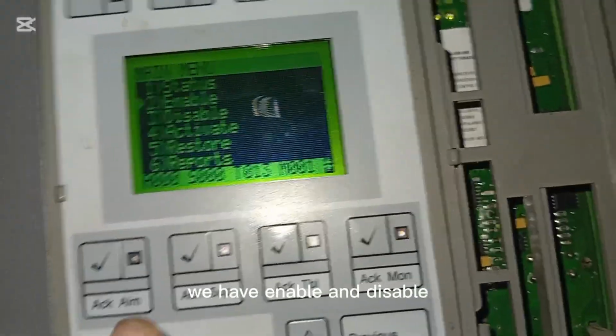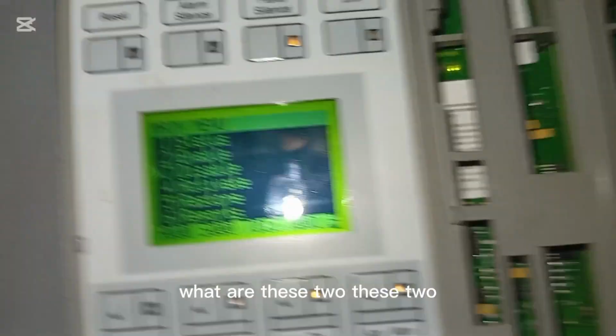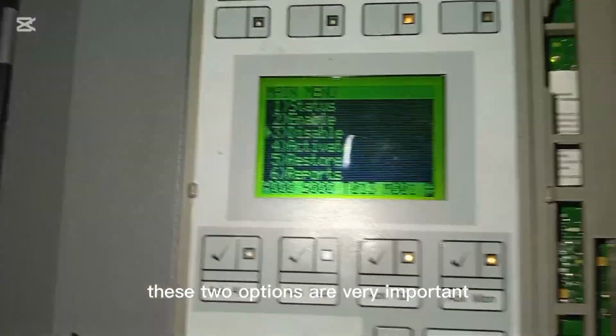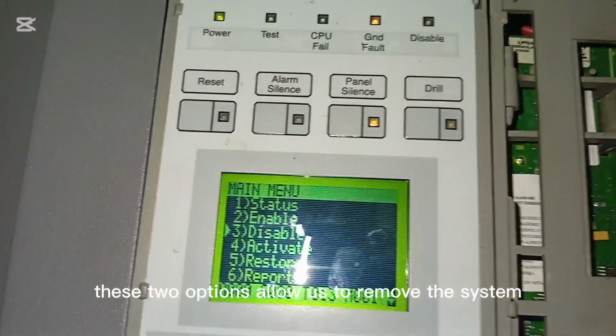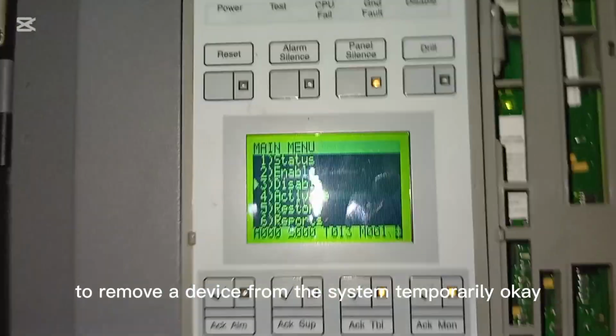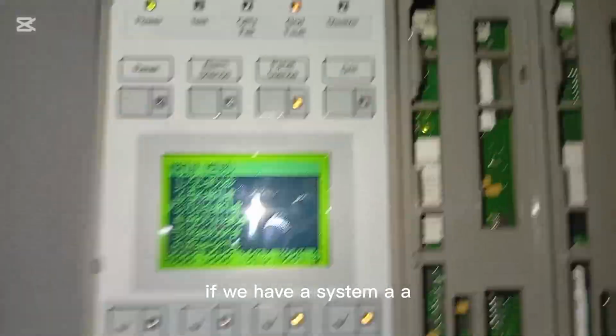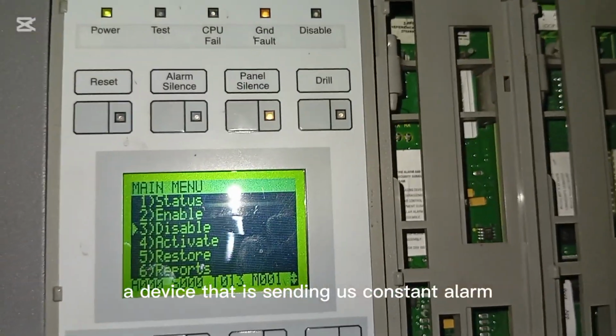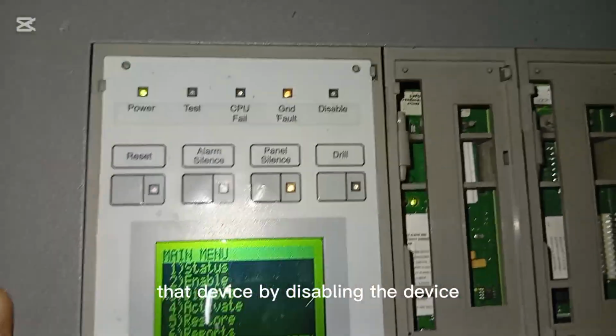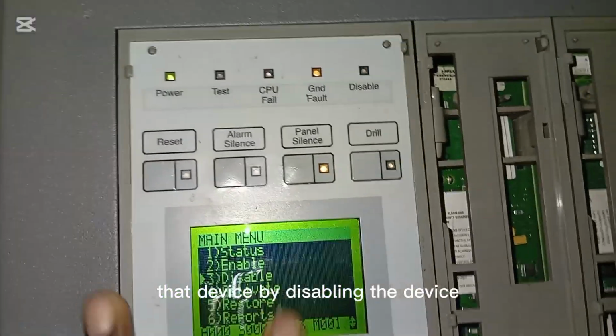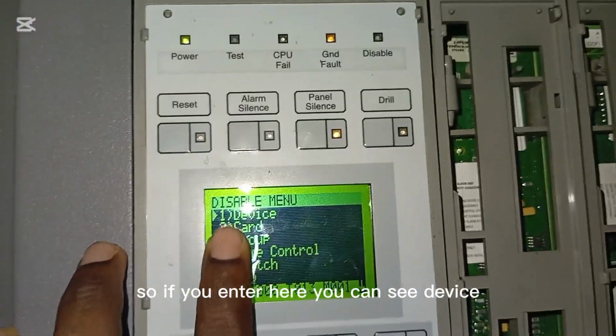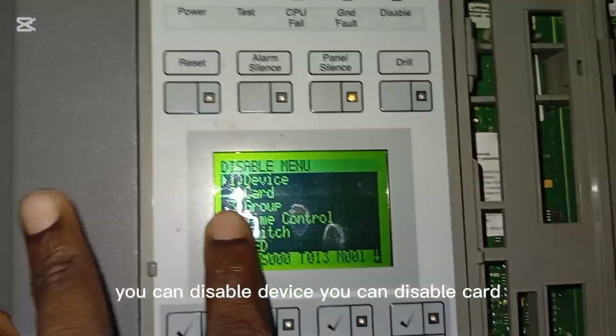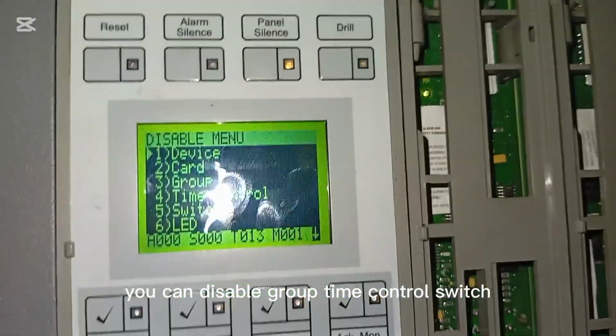If you come here, you have enable and disable. What are these two? These two options are very important. They allow us to remove a device from the system temporarily. If we have a device that is sending us constant false alarms, we can easily isolate that device by disabling it. If you enter here, you can see you can disable a device, a card, a group, a time control switch, and so on.